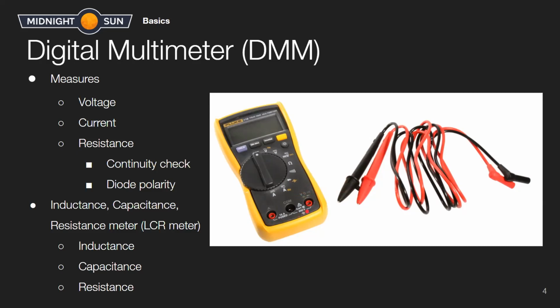And there's a limit, so each DMM will have a limit of the rated voltage that it can withstand. So this is 600 volts between the common terminal and this terminal. The other terminal is used for current measurements. And this one has a 10 amp fuse in this DMM.